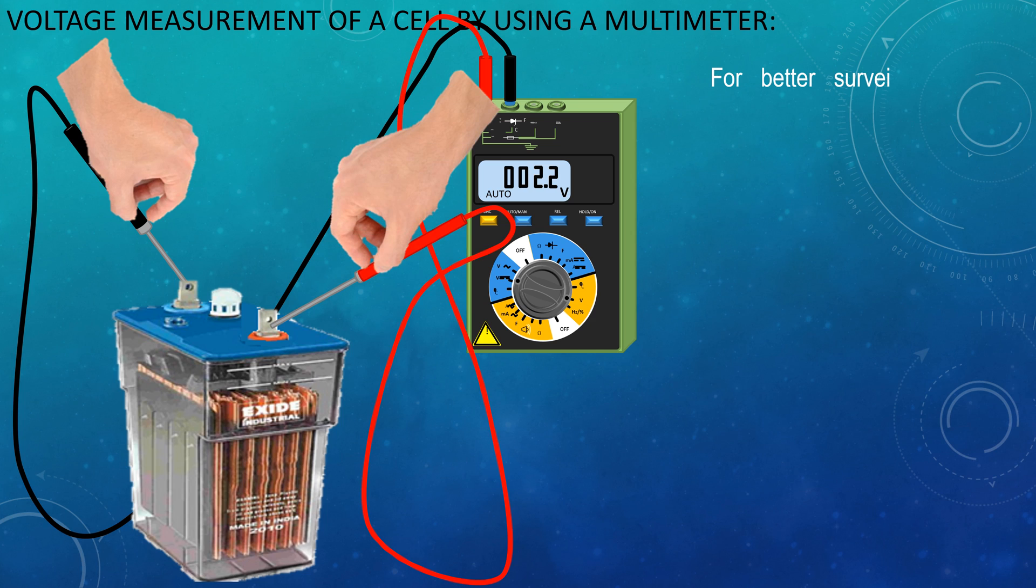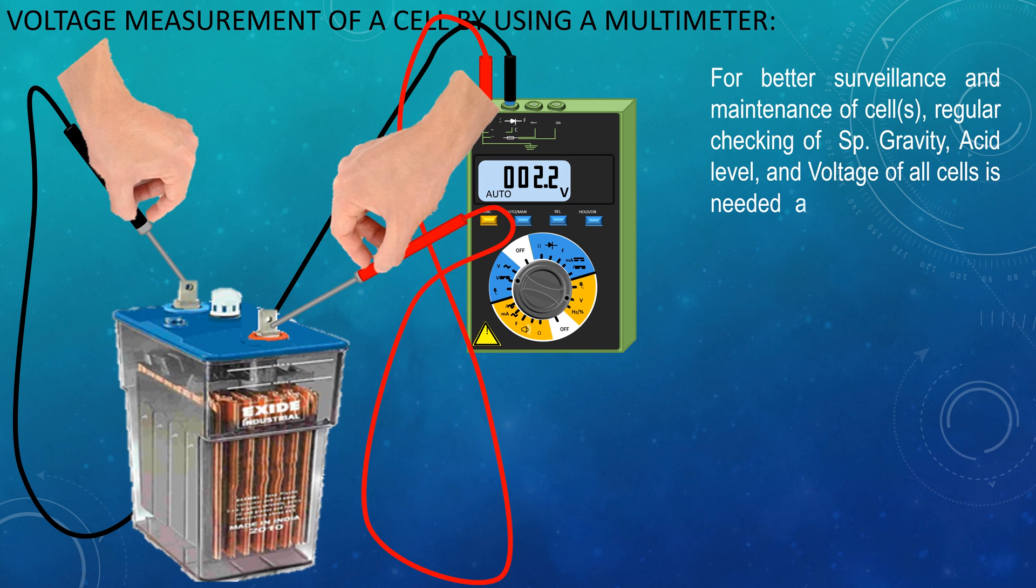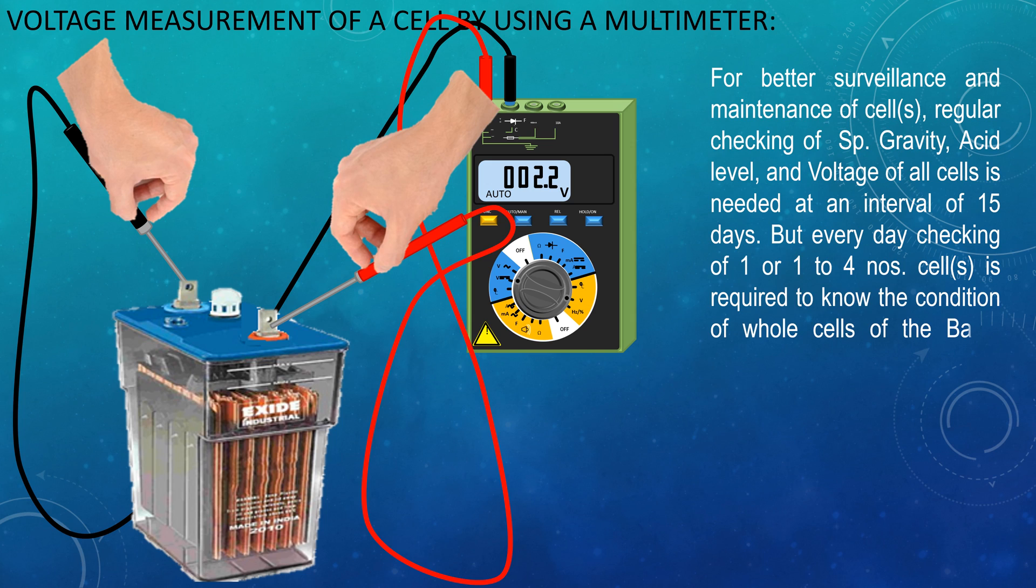For better surveillance and maintenance of cells, regular checking of specific gravity, acid level and voltage of all cells is needed at an interval of 15 days. But everyday checking of 1 to 4 number of cells is required to know the condition of whole cells of the bank. This 1 or 1 to 4 number cells is termed pilot cell. The pilot cell will describe primarily the conditions of whole cells of the bank.